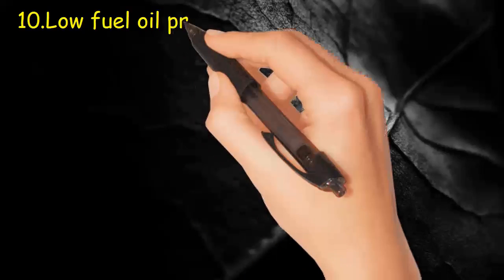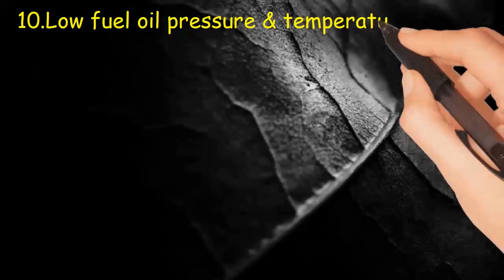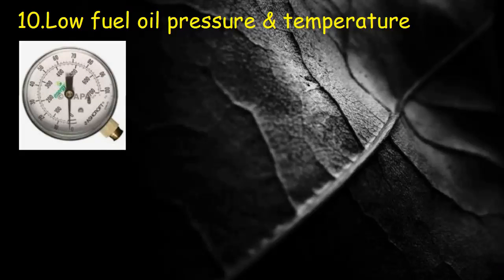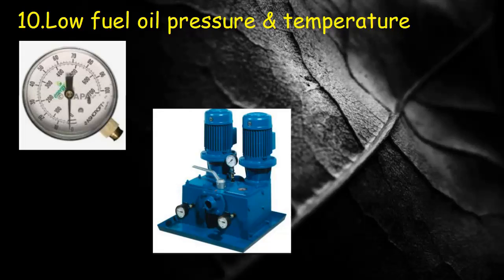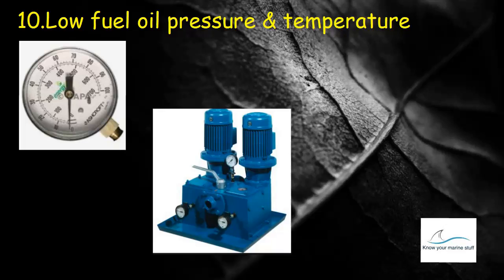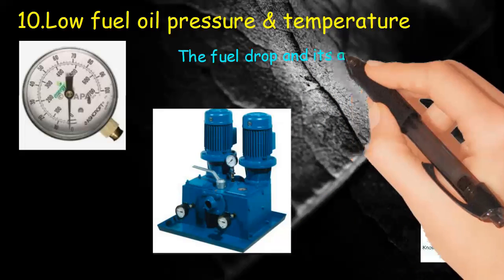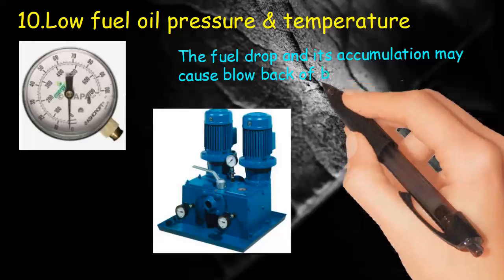Low fuel oil pressure and temperature. If fuel oil pressure is less than normal, then atomization will not be proper and oil will drop in furnace. Two pumps are provided so there will be no problem in normal operation of boiler. If fuel pressure drops, alarm will come and cause of drop must be rectified as soon as possible. The fuel drop and its accumulation may cause blowback of burner.